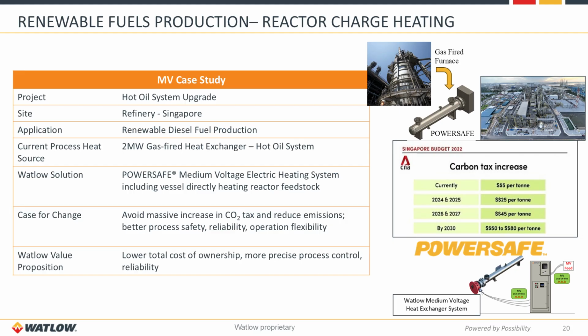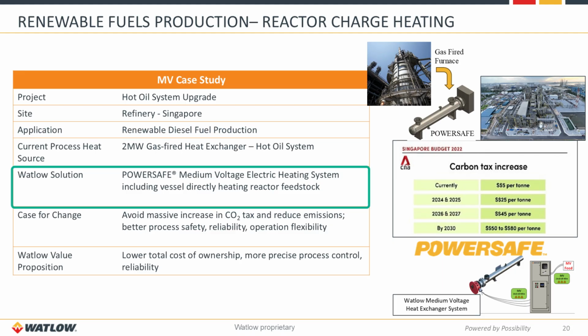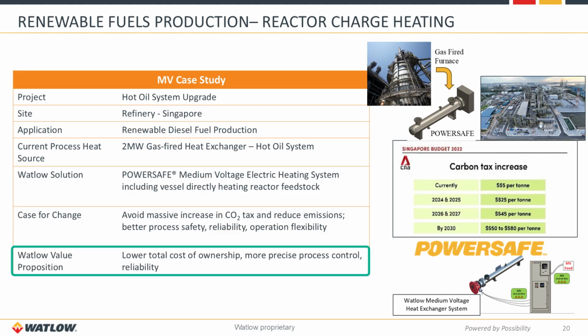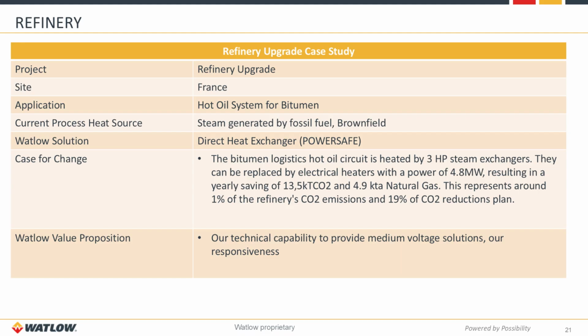In this particular case, it was renewable diesel fuel production. We had a 2 megawatt gas-fired heat exchanger in the system that was currently operating. We replaced that with a POWERSAFE medium voltage electric heating system, included the vessel, the heater, and the controller to install to replace that gas-fired heat exchanger. The overall value proposition obviously was lower total cost, more precise process control, reliability in the system, and obviously less carbon emissions. The next one we'll go through is a refinery upgrade in France.